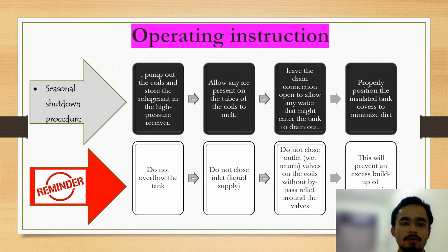For the next part is operating instruction. For the seasonal shutdown procedure, the first step is we must pump out the coils and store the refrigerant in the high pressure receiver. Next, we must allow any ice present on the tubes of the coils to melt. And then we must leave the drain connection open to allow any water that might enter the tank to drain out. And lastly, we must properly position the insulated tank covers to minimize dirt.